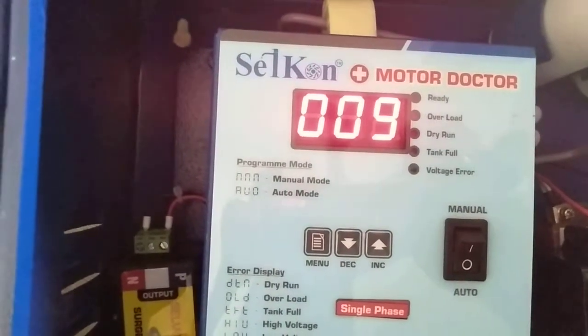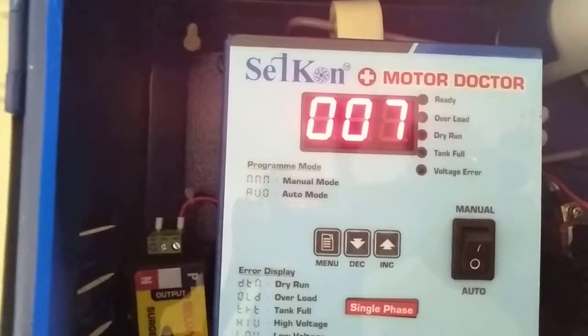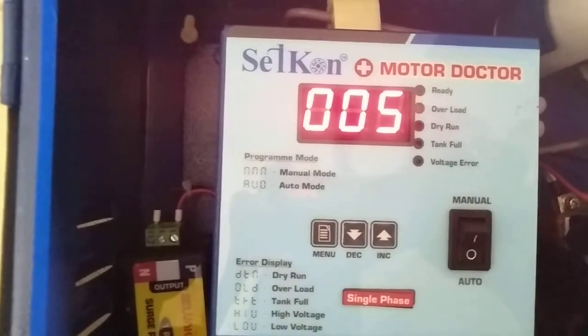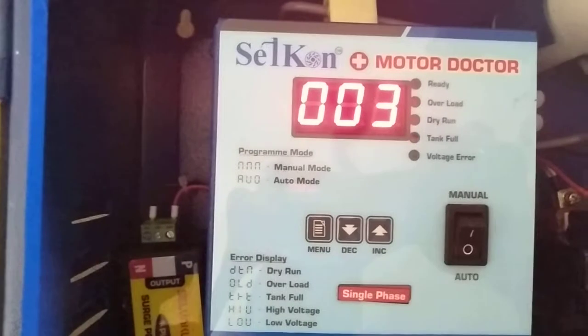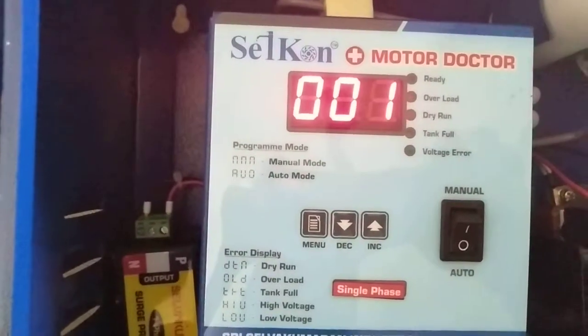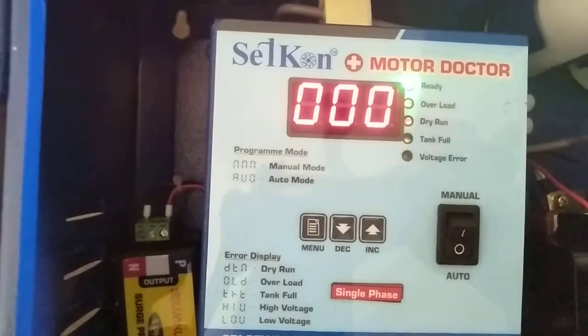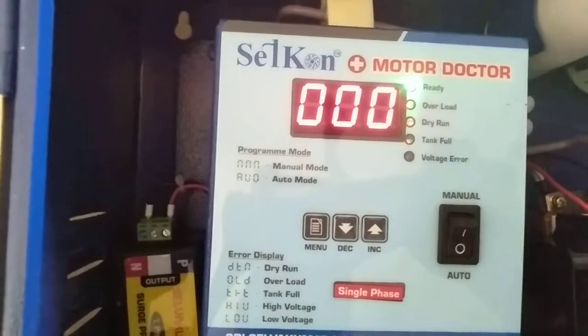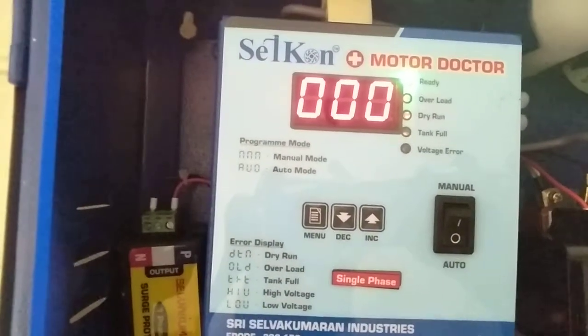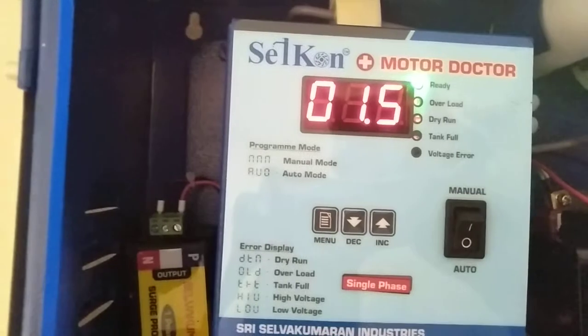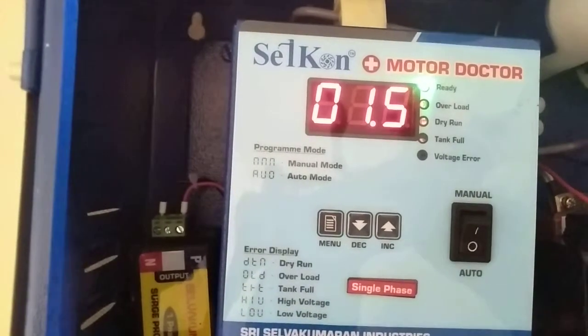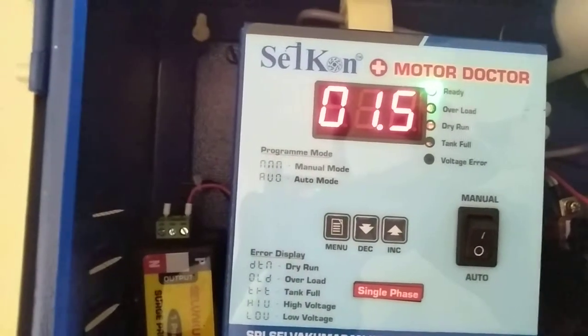So now we have already fixed the Autostart time as 10 seconds. Once it reaches 0, the controller will switch on automatically. So now it reaches 0. Now the ready light is on. Now the motor is started. We have already connected a 1 HP motor, so automatically it takes 1.5 amps.